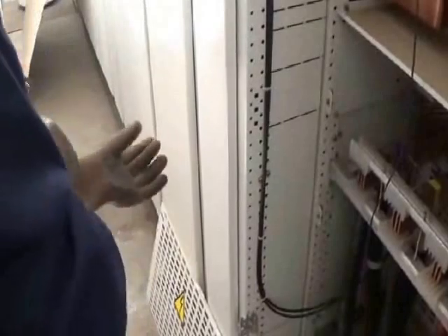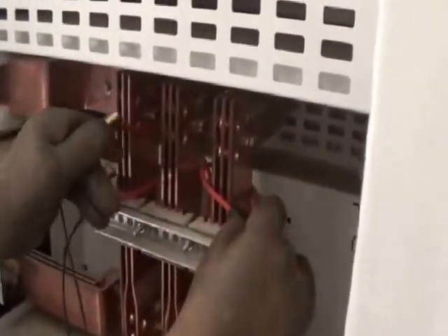As you can see, we have the current transformers. That is a current transformer being put. It is going to be used to measure the current, and so it's a three-phase equipment where measurements are taken from all the lines, line 1, line 2 and line 3, including the neutral. So the glove has to be put on, and then one of the current transformers is set up. Those are live bus bars, so it has to be put in a particular direction for accurate recording of data.